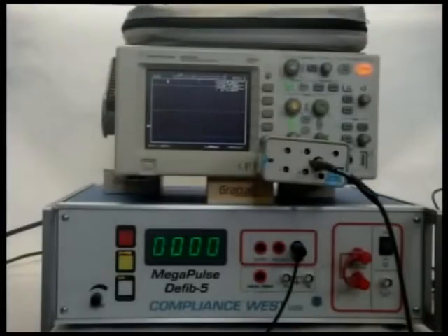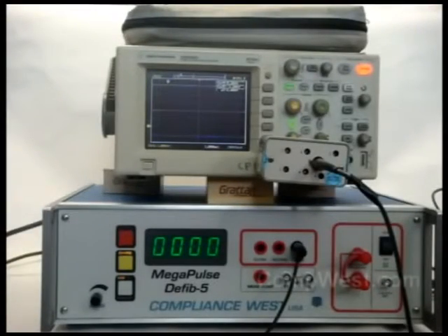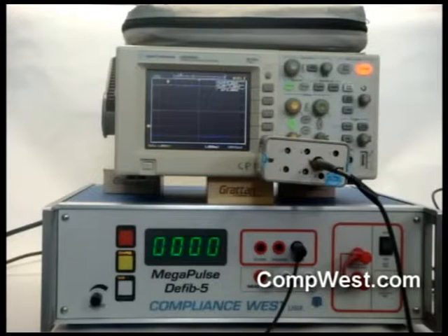This video will talk about IEC 60601 energy determination with the Defib 5 using the Excel method. IEC 60601-1 Issue 3, paragraph 8.5.5.2 outlines the procedure to conduct the energy reduction test to test the delivered defibrillation energy when the device under test is also connected.